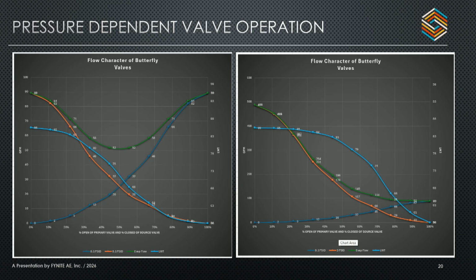And the butterfly valves are not very linear, especially in that first 25% range. So you get essentially no flow from the one that has low pressure and a significant amount of flow from the one that has high.